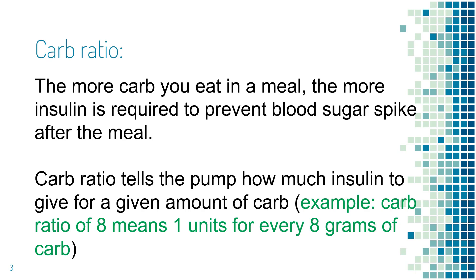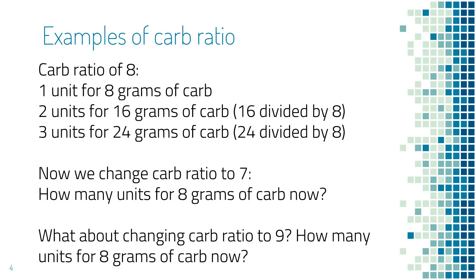For example, a carb ratio of 8 means giving one unit of insulin for every 8 grams of carb. If the carb ratio is set to 8, the pump gives 1 unit for 8 grams of carb (8÷8=1), 2 units for 16 grams (16÷8=2), and 3 units for 24 grams (24÷8=3). The pump divides the carb number by the carb ratio number to get the insulin amount.